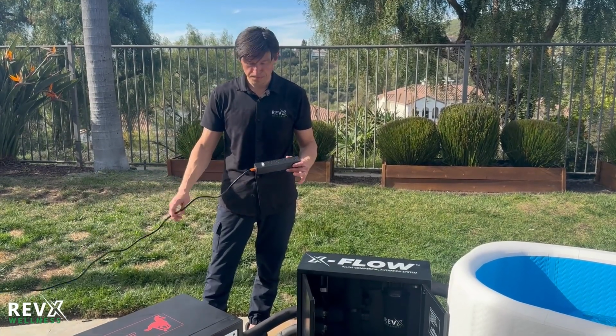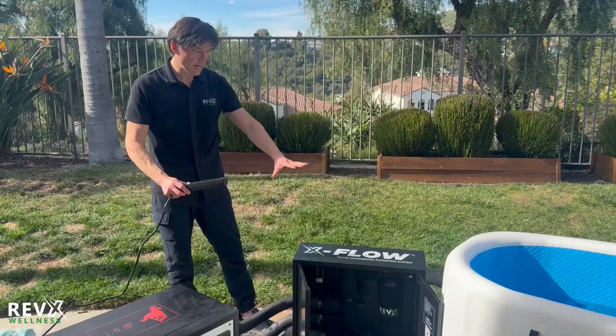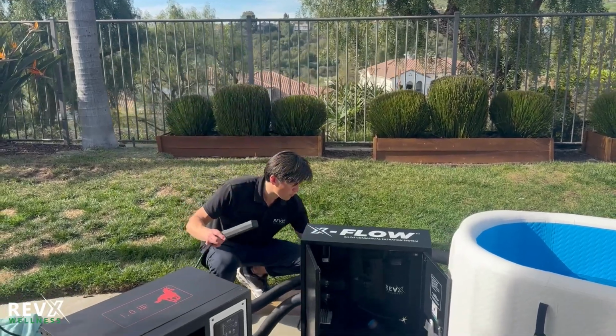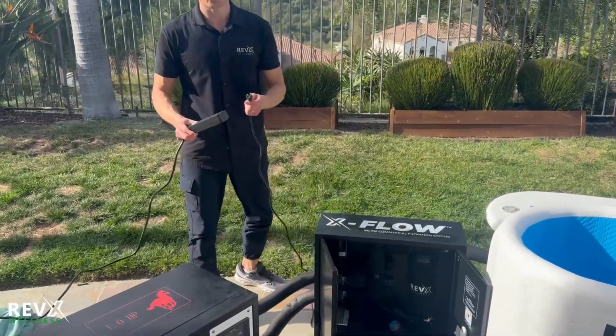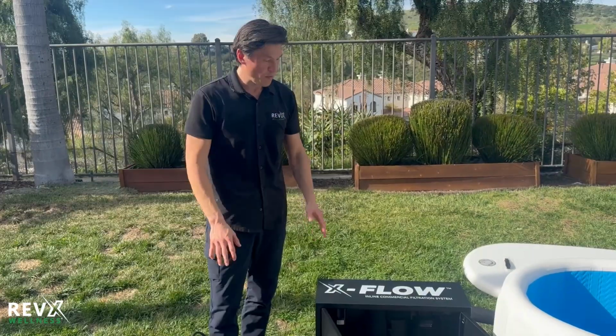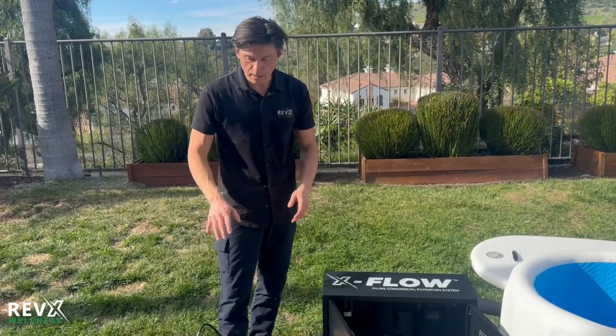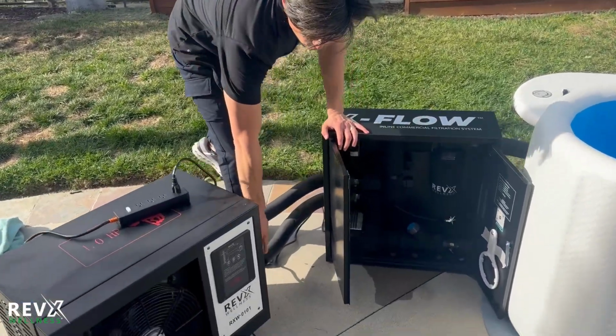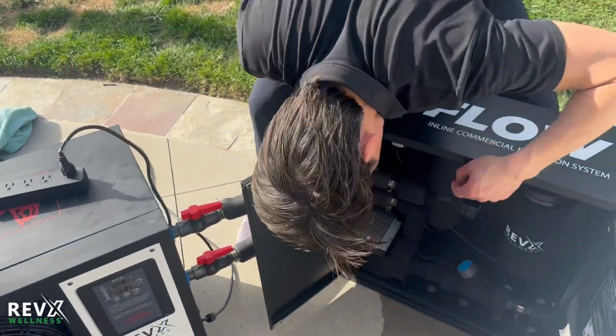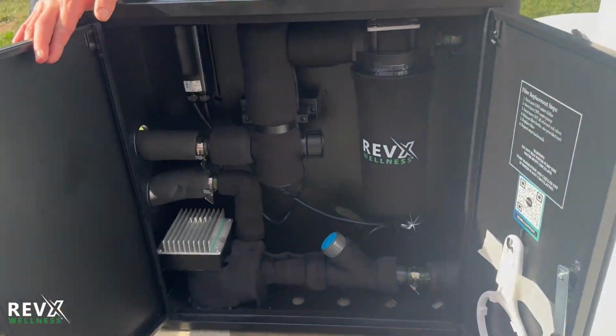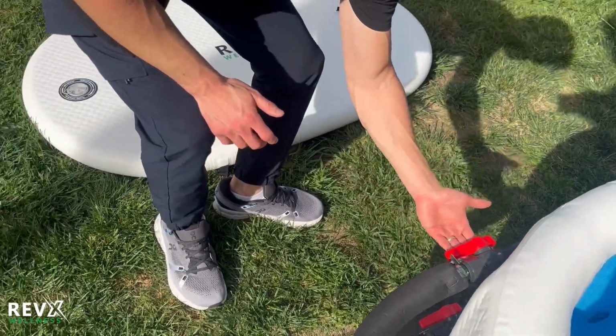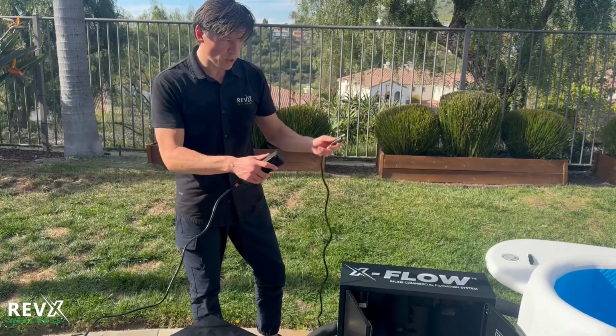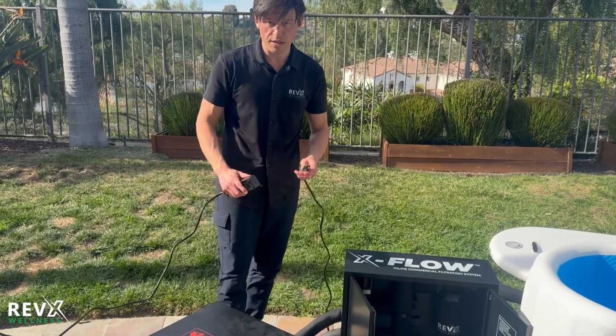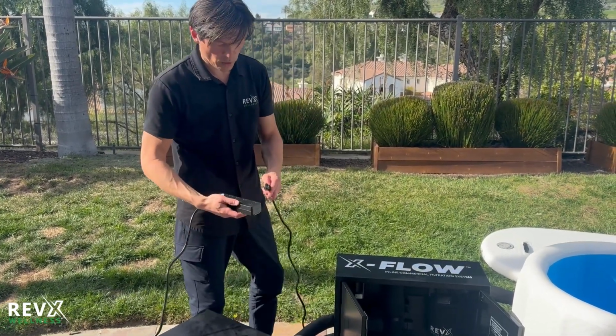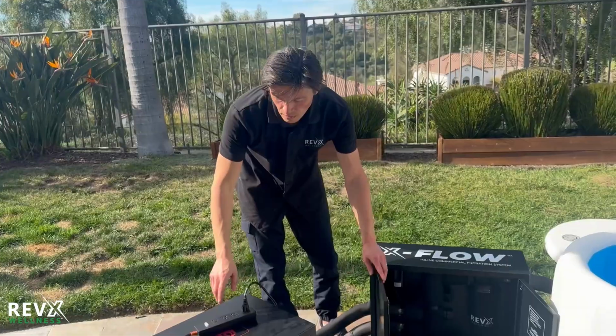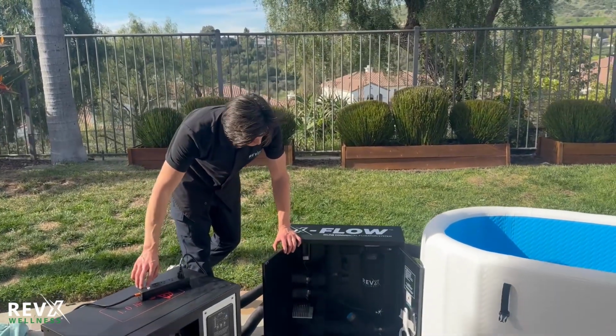It's very important. When you connect the system to power for the first time, make sure that you start with the pump only. Before you turn on the power strip, make sure that all the rad valves are in the open position. These are all open, they're all parallel, because we want to confirm that the water is flowing before we connect the chiller to power. So what we're going to do is we're going to connect it to power. Now let's turn on the pump.